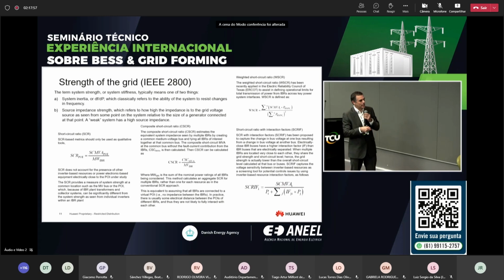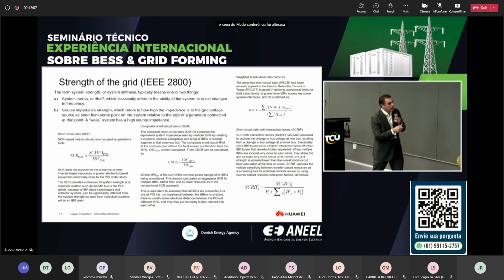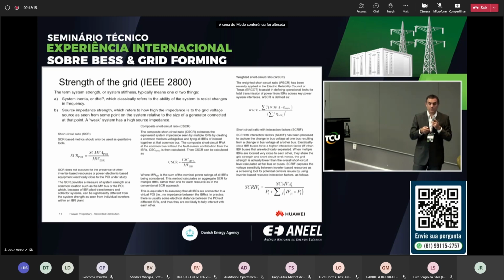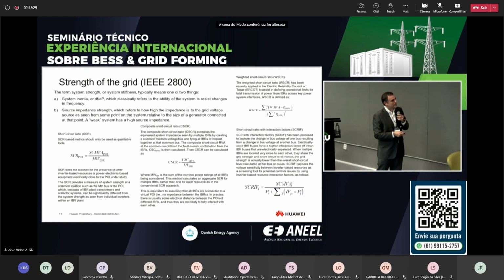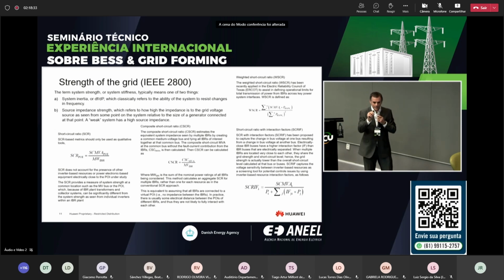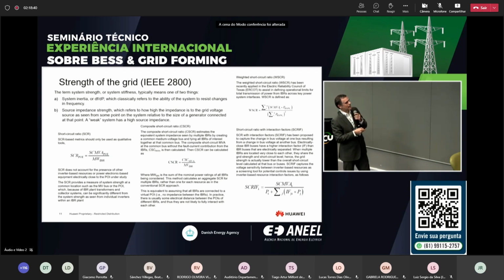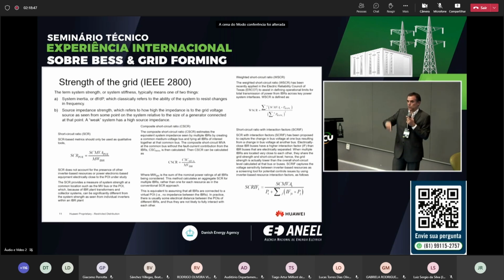Many people are thinking about that, defining composite short circuit ratio or weighted short circuit ratio, whatever. There's one that's very interesting, considering interaction factors between different plants. The interesting thing is that Brazil's ONS is using that in some analysis I saw, for analyzing or detecting where the weak buses are in the grid. The definition is that a weak system has high source impedance, meaning that if you put some current on it, the voltage will move a lot.